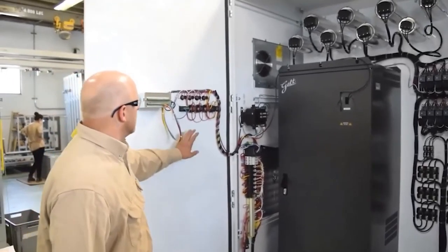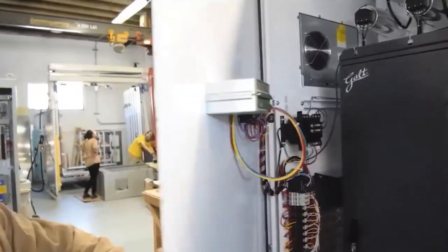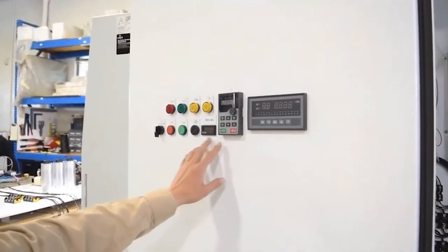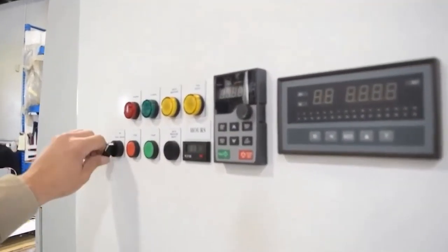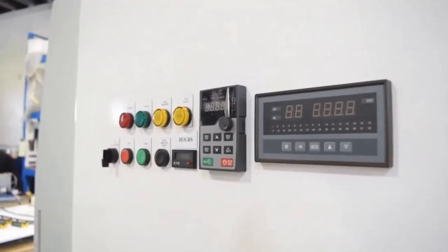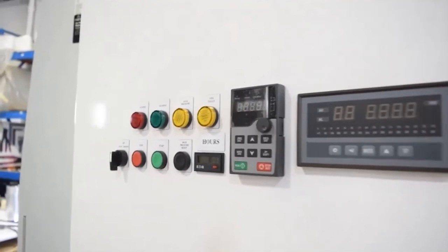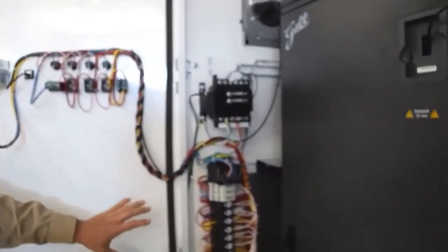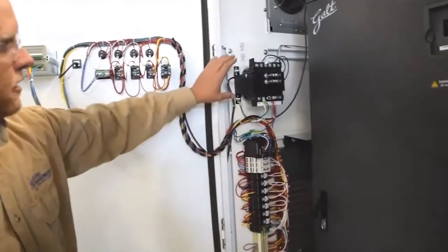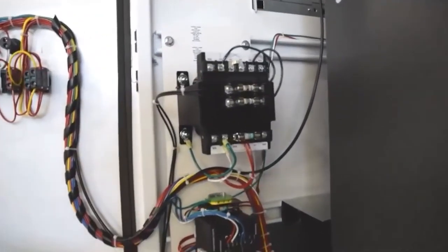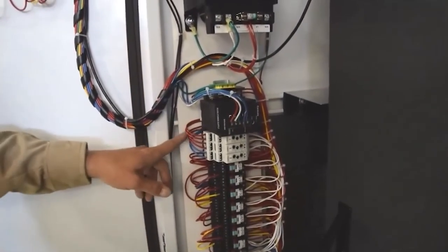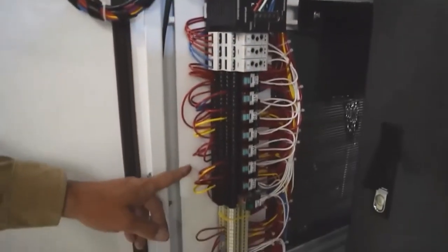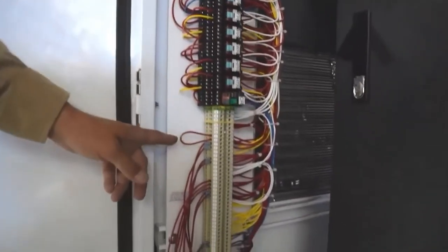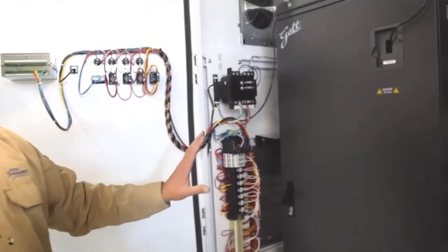So the first thing I do is kind of explain what's going on inside the cabinet. We got our instrument cluster on the front, similar to like Craig showed. We have your keypad for the VFD. You got some push buttons, selector switch, and some lights. And we're going to get inside the cabinet, and the first thing that we're going to see over on the left-hand part of the cabinet, we're going to see our control power transformer. It's going to take your 480 volts down to 120. We got a 24 volt power supply, got some time delay relays, we got our ice cube relays, and then we got a terminal strip. Terminal strips for all the incoming connections.